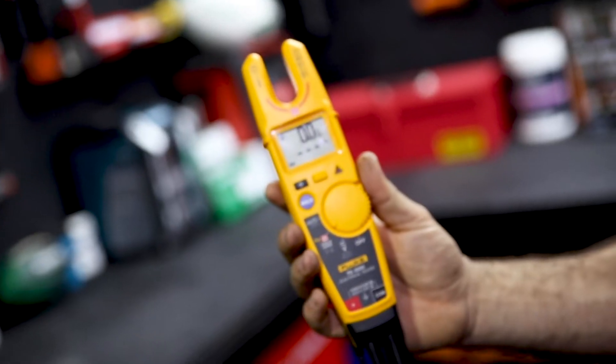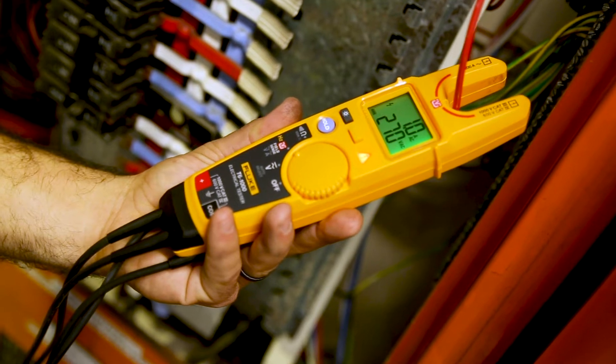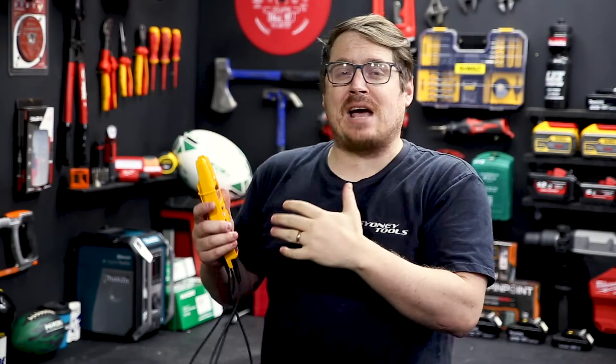Check this out — this is the T6-1000 Electrical Tester from Fluke. This true RMS meter features FieldSense. You can measure up to 1000 volts AC through that fork up top without the use of test leads. That means no probing, no making contact with metallic conductors when it's not necessary. It's faster, it's easier and it's safer.